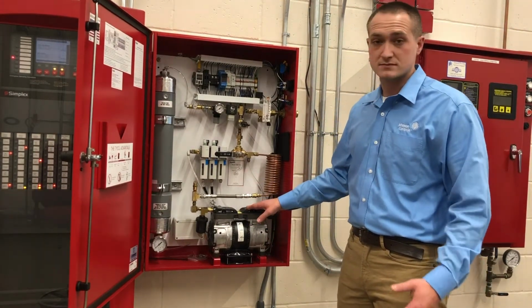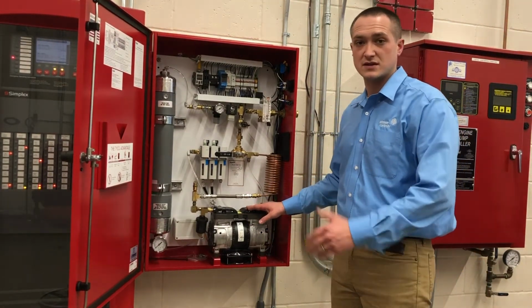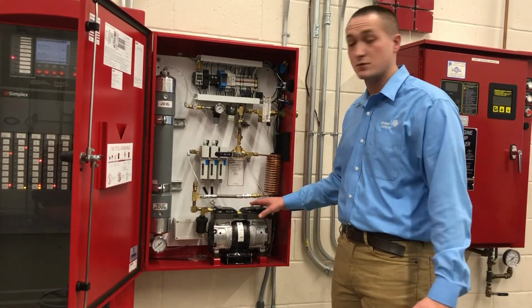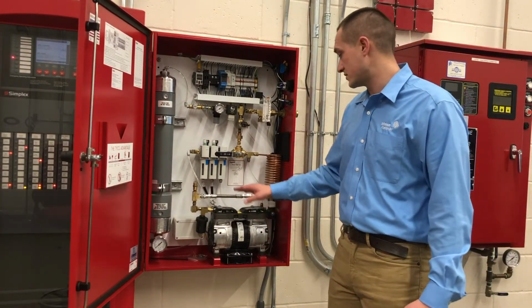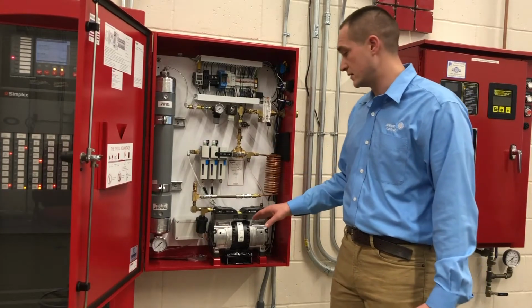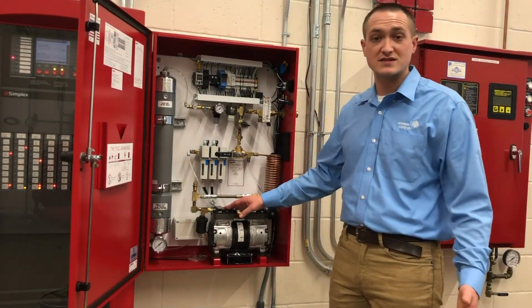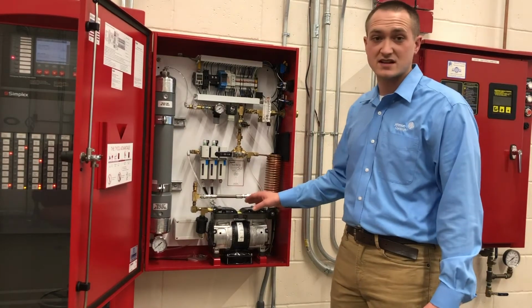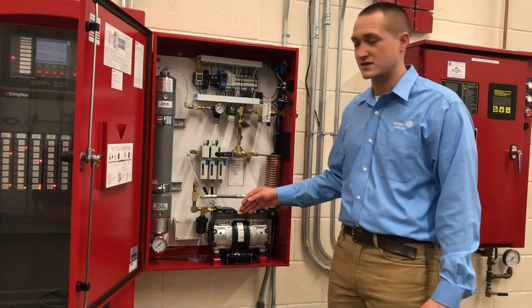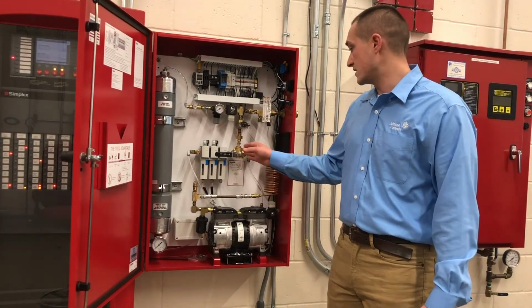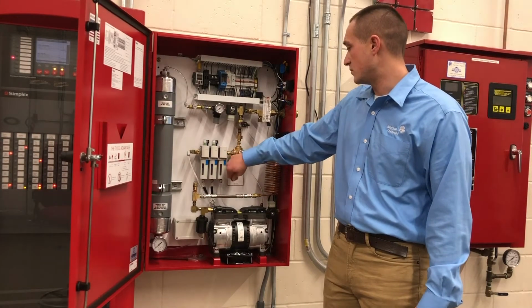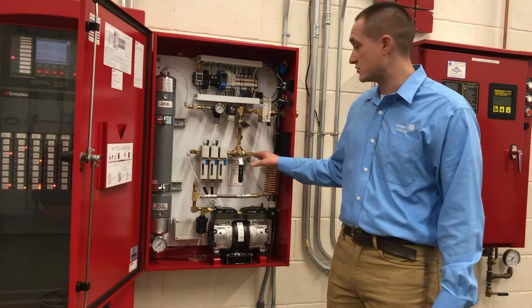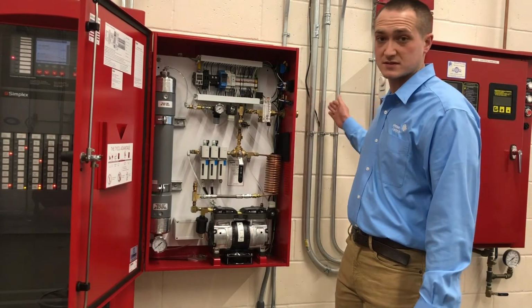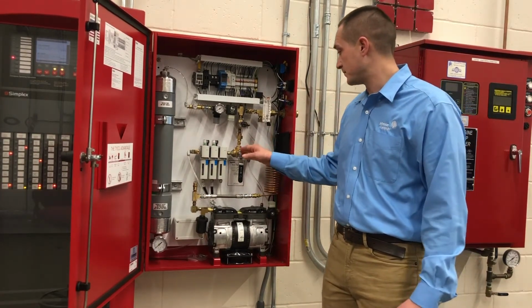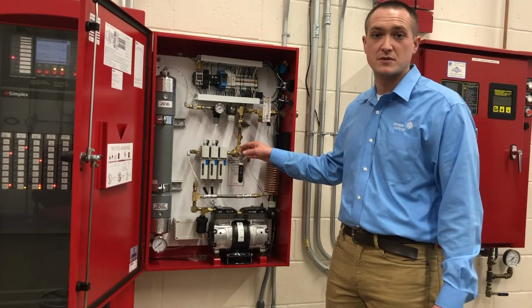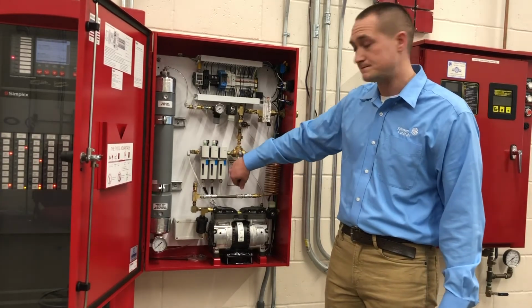We'll have a compressor. The compressor will vary from this unit to the standalone and skid mount unit, but there will be an air compressor. This air compressor leads into a coil. When you compress air, you increase heat. So this coil is here to dissipate that heat that we produce when we're compressing the air. The air then leads through this ball valve. You have bypass mode. Bypass mode directs air directly into our sprinkler systems. This allows us to fill our systems within 30 minutes as per the standard.